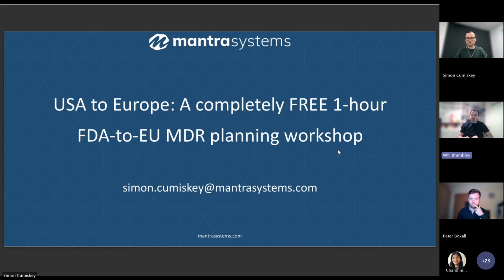You did touch on timelines as well, Simon. You said the expected time largely is somewhere between 13 and 18 months for most manufacturers, or that's been their experience recently. That's certainly not to say that can't be done quicker. And there are some notified bodies where you can get estimates of anywhere from 3 months to 9 months. And all the things I mentioned that will influence cost will also influence the time as well.